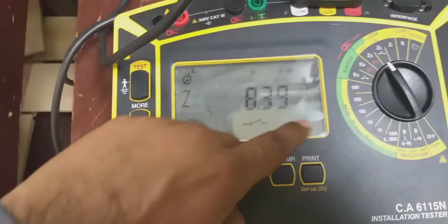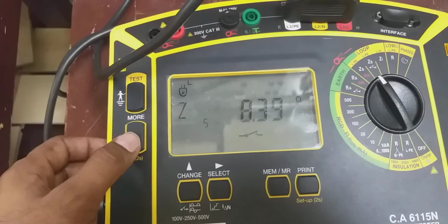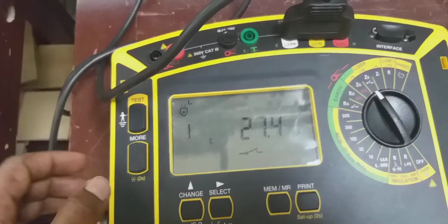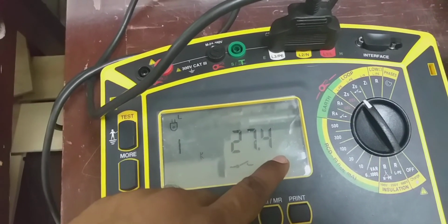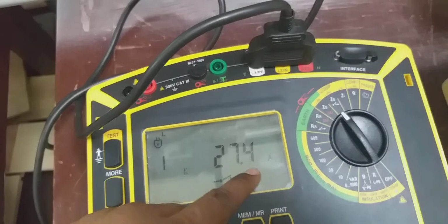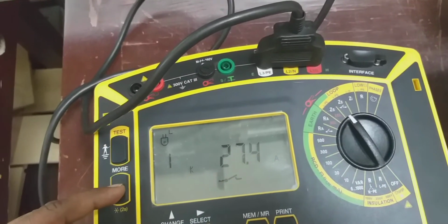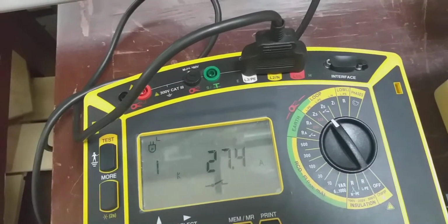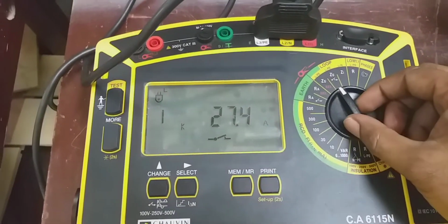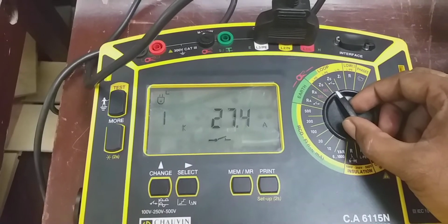So you can see here it is mentioned Z, and this is the value, and here the unit is ohms, right? So the next one is the short circuit current. Press this button more, you will get the short circuit current as 27.4 amperes. Okay, so this is the earth fault loop impedance and the short circuit current of this particular installation what we made.